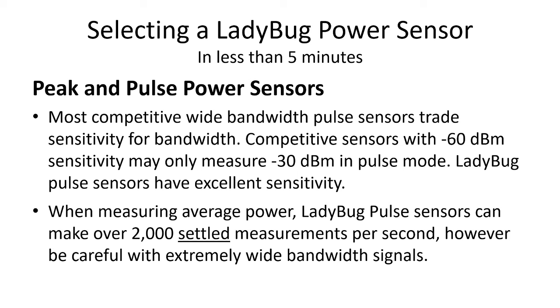So if you have a signal that has a modulation bandwidth of 10 megahertz or so, you can use one of our sensors and get a great pulse measurement. You can also use the sensor for making very fast average power measurements. So if you're testing an antenna or you're testing a source and you need a lot of measurements, you can make 2,000 settled measurements per second with any of our pulse sensors.